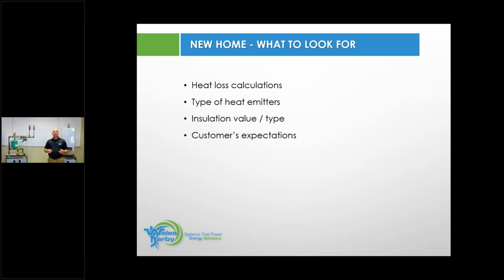And then we really want to understand the customer's expectations. You're going to go in there, do a heat load calculation. You're going to ask about the shower. How are they going to make hot water? So you go in there and do your standard install. Let's say it's a boiler and a 45-gallon indirect. Great.